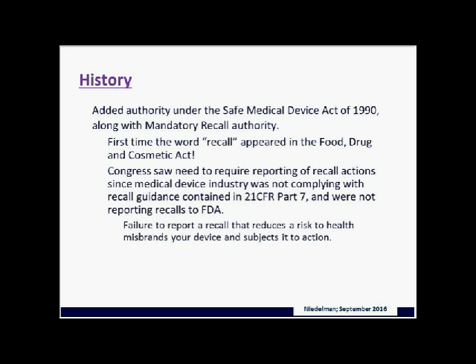As I mentioned earlier, this came about because Congress was seeing that the industry was not abiding by the guidance document to report recalls. This was the first time the term recall ever appeared in the Food, Drug, and Cosmetic Act, in 1990. But they saw the need to require reporting to FDA so that FDA had a thumbprint on how industry was doing, how products were performing in the marketplace, and that failure to report in a timely manner misbrands your device and is subject to legal action, aside from the problem associated with your device that may also subject it to legal action.